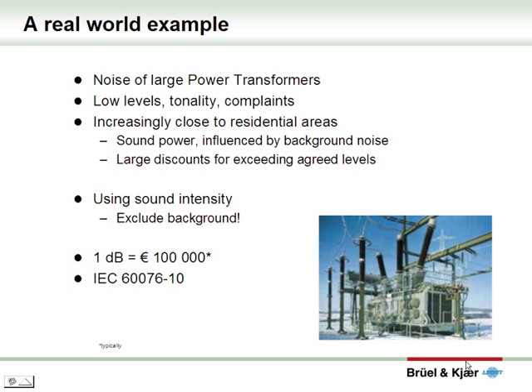Here's a real-world example. Suppliers of large power transformers promise low noise levels to their customers, because transformer noise often causes complaints. After the transformers are placed, if the noise levels are too high, they're not removed or replaced — instead, the customer will get a discount. So it's up to the manufacturers to prove that the sound levels are sufficiently low, and it's valuable to have a measurement method which excludes all extraneous background noise. Sound intensity will do that, and often a reduction of one decibel could avoid very hefty fines. Please read the IEC standard mentioned on the sheet.